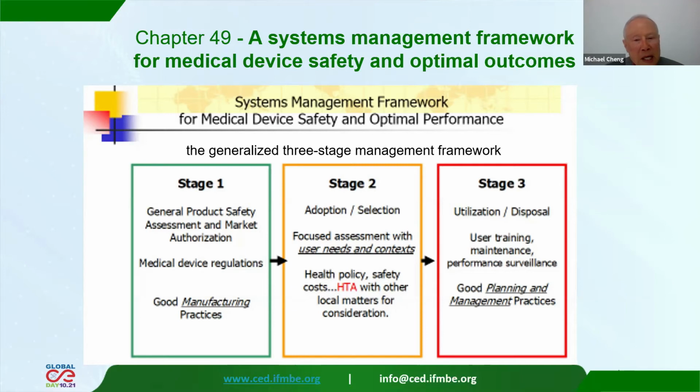If we look closely, this management framework is actually a graphic implementation of the World Health Assembly Resolution 60.29. The framework can serve as an educational framework for all stakeholders to recognize the complex role of clinical engineering. And in step 3, very important is the good management practice, where, if you look into the detail of this chapter, the 10 essential elements are based on quality management system concepts, the ISO 9000.